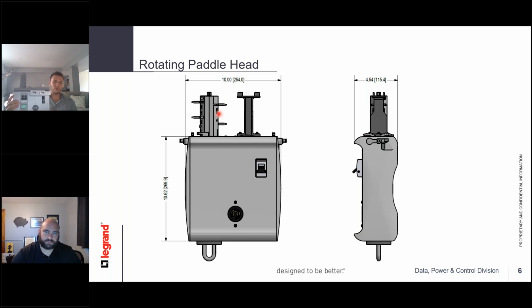You know, so if there is a lot in the way, say you got a wall behind you that's in the way, and let's say you have a rack in front of you that's in the way, you don't have to worry about spinning this. You put that up in there, and like Corey mentioned, you turn that bottom piece on there, that bottom hook with a lever, and that locks this into place. And it's already locked up into place on the end, supported mechanically, because of your two claw designs on the sides.